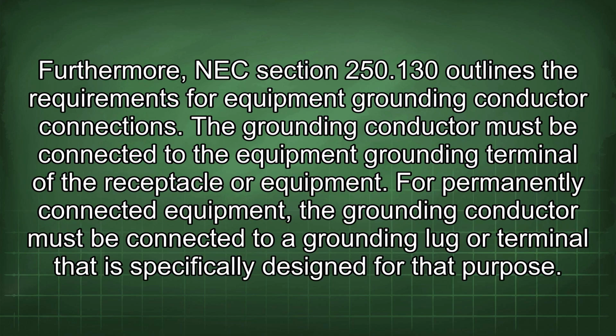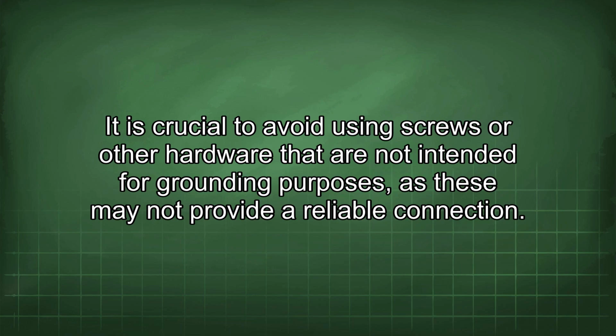Furthermore, NEC Section 250.130 outlines the requirements for equipment grounding conductor connections. The grounding conductor must be connected to the equipment grounding terminal of the receptacle or equipment. For permanently connected equipment, the grounding conductor must be connected to a grounding lug or terminal that is specifically designed for that purpose. It is crucial to avoid using screws or other hardware that are not intended for grounding purposes, as these may not provide a reliable connection.